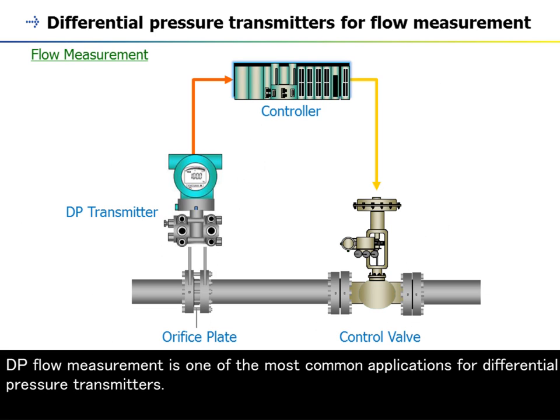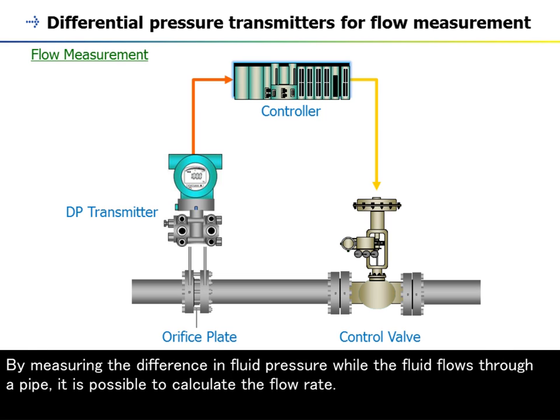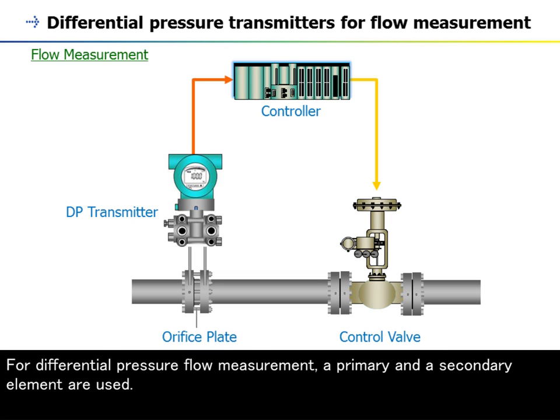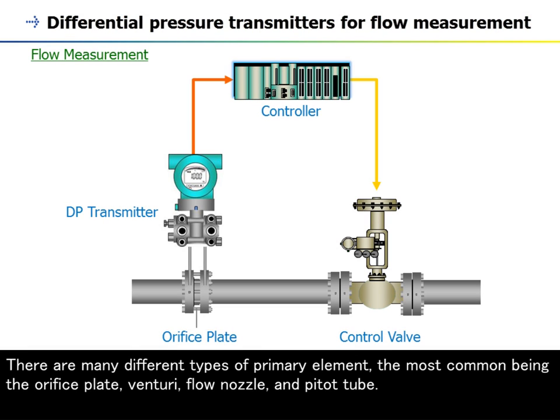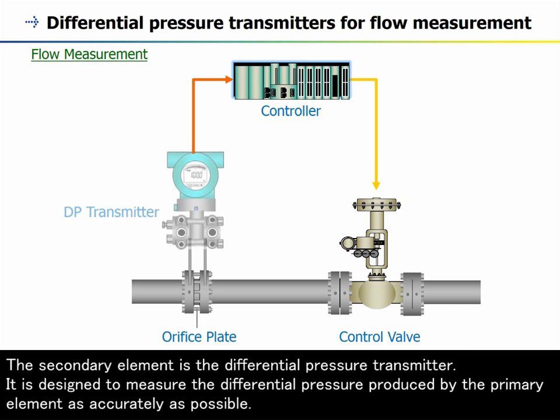DP flow measurement is one of the most common applications for differential pressure transmitters. By measuring the difference in fluid pressure while the fluid flows through a pipe, it is possible to calculate the flow rate. For differential pressure flow measurement, a primary and a secondary element are used. The primary element produces a difference in pressure as flow increases. Common primary element types include the orifice plate, venturi, flow nozzle, and Pitot tube. The secondary element is the differential pressure transmitter.